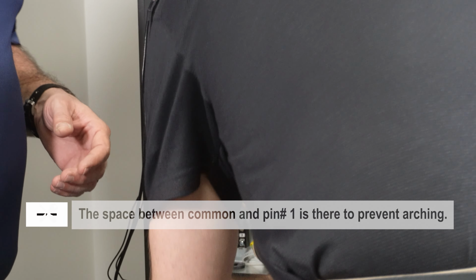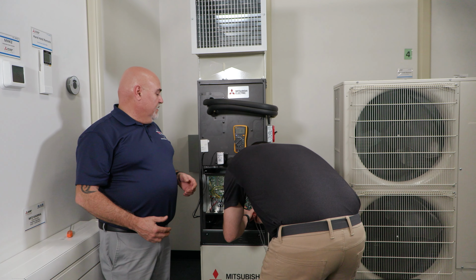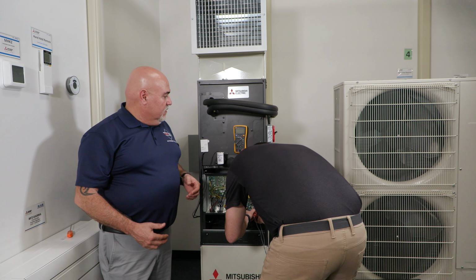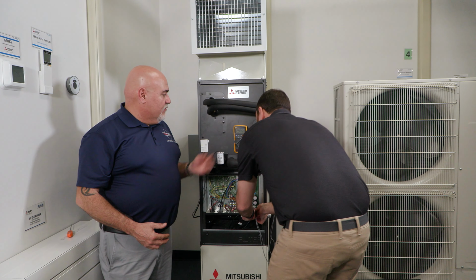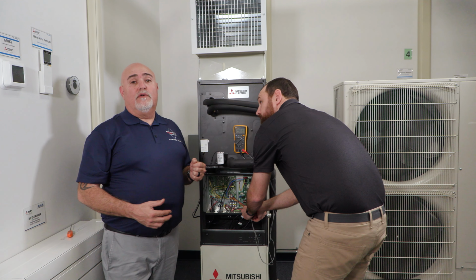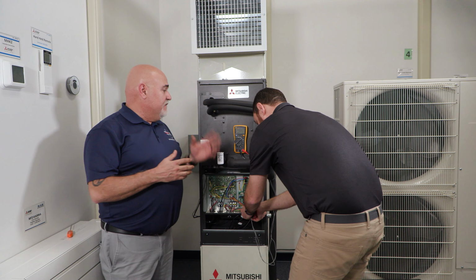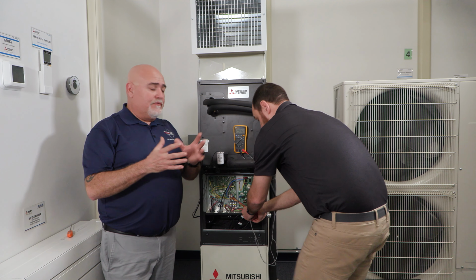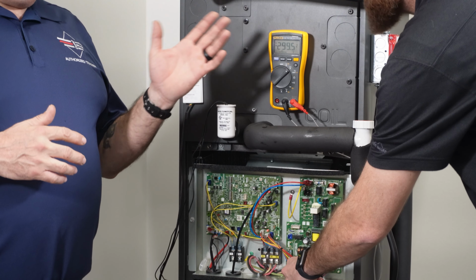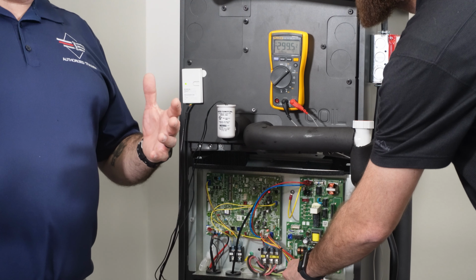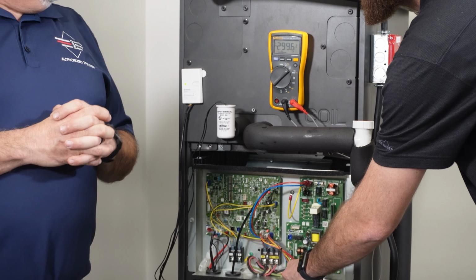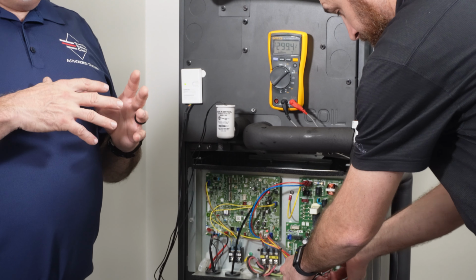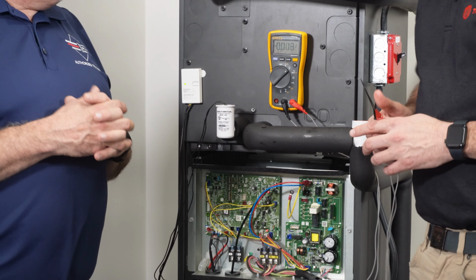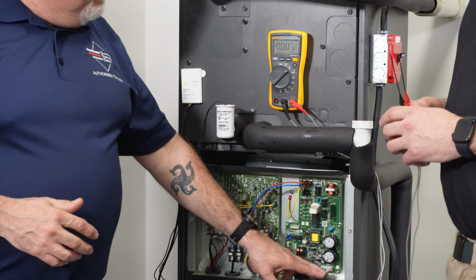So let's do that, Scott. We're going to go between 1 and 4. Right now we have 299.4 volts, so we're good. We're just looking at a ballpark of 300 volts, and that 300 volts in the system is based upon incoming AC voltage. So if you have a lower incoming AC voltage, you may have a lower DC voltage, but we're in the ballpark of 300 volts.